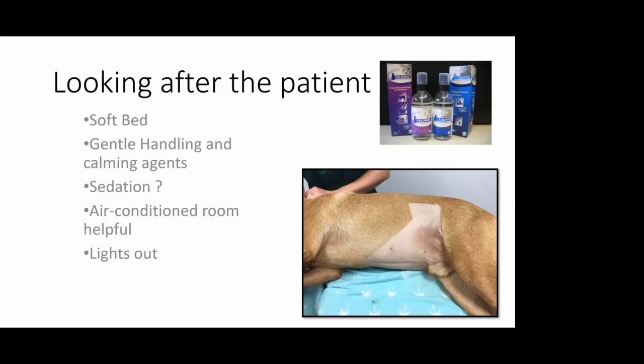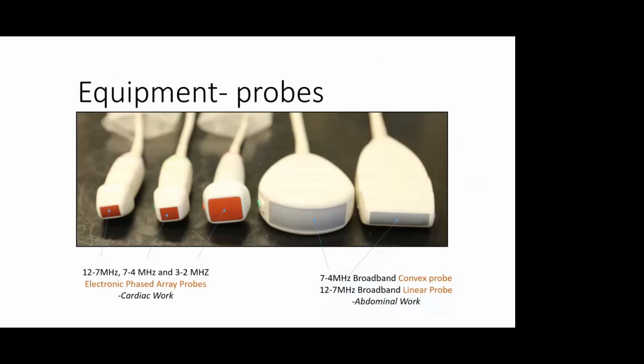So if we talk about probes, ultrasound machines come with lots and lots of different choices probe-wise. But if we were just going to have a look at the go-to probe that you would want for doing an abdominal ultrasound scan, I would be thinking about a microconvex probe that is capable of running at a middling range. So, sort of between 8 and 4 megahertz maybe. And that would be the sort of probe that will do most of your abdominal ultrasound scan.